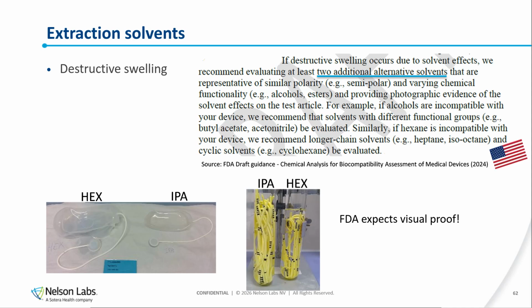Now, sometimes you do not have compatibility between your solvent and a device. And unfortunately, you can have destructive swelling. Destructive swelling is a problem because the extractable profile that you will see is not representative of any real use. It's too exaggerated. You're breaking down your device, and this will obscure a lot of the wanted extractables that you want to see. So that's not good.